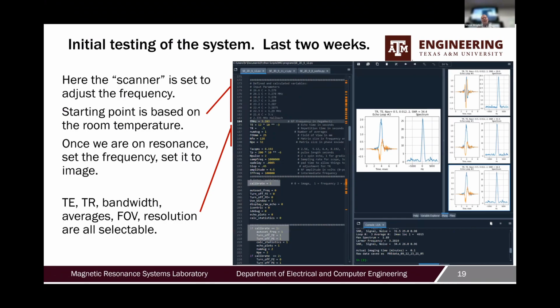So system's built now, it's time to test it. And so here's an example. All right, so here we're adjusting the frequency. So you probably can't read this stuff, but it says calibrate equal 1, which means adjust frequency. And if calibrate equal to 1, it turns off the gradients. And when you ping the system, I told it to ping it 3 times. First time it's off resonance, then it moves to the resonance and prints out the frequency. You then enter the frequency up here, turn off calibrate, set that equal to 0.